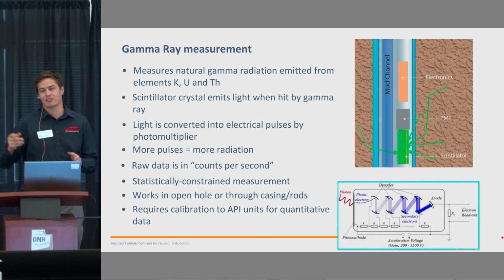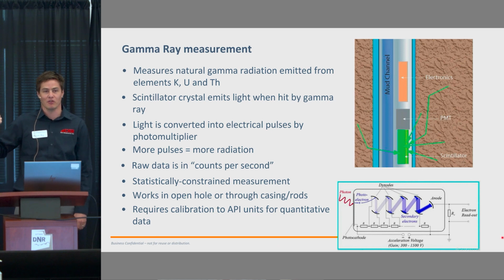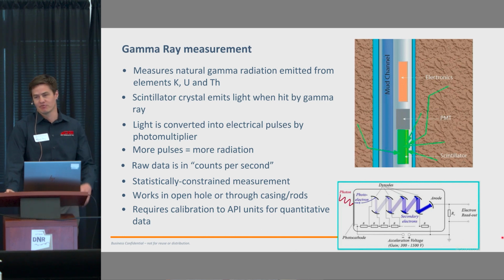So to calibrate, it's really easy. There's just calibration holes, like there's some down in Grand Junction that are controlled by the DOE. They put those in for uranium logging, for measuring, for looking for uranium. And you see how much radiation it's emitting, you see how many counts per second, and you just write a new calibration equation that relates counts per second to the standard unit, which is API.